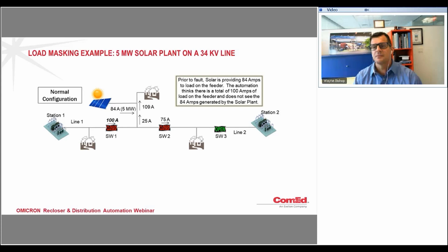And part of the issue that's come up is load masking. I kind of want to go a little bit into what the load masking issues that we're seeing are. So on a 34 kV line, to have 5 megawatts of solar, in the example that's on the screen right now, contributes about 84 amps to the section of line between switch 1 and switch 2, with some load supplied by the utility, for a total of 109 amps in that section between switch 1 and switch 2. The automation at the switches only reads a 25 amp contribution from the utility. So the automation is only thinking that there's 25 amps of load in that section of line prior to a fault, with an additional 75 amps between switch 2 and switch 3.